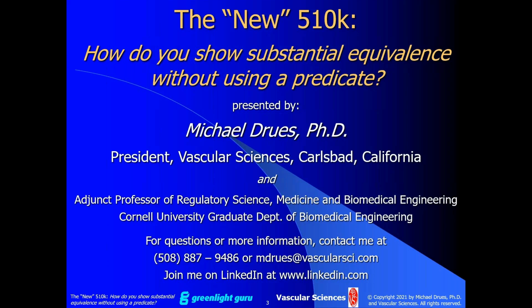510K exempt. Well, Lars, good question. If I understand your question, the word exempt in that context means you are exempt from a formal review of your device by the agency. In other words, I don't like the phrase 510K exempt. I think the better phrase is Class 1 or Class 2 exempt.